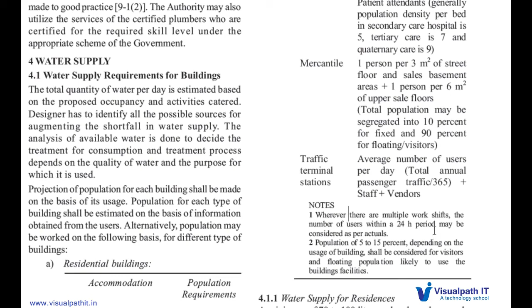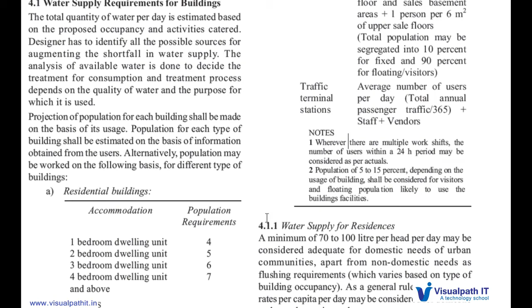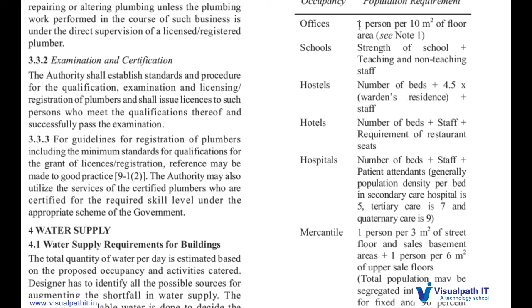In the notes, wherever there are multiple work shifts, the number of users within the 24 hour period may be considered as per actuals. So how are we considering it? For example, for a bedroom, one bedroom we said four persons. Sorry, not for residential. This note is for office buildings, hotels, and hospitals under other than residential. For offices, we have considered one person per 10 square meters. If there is day and night work, we need to consider two persons per 10 square meters.